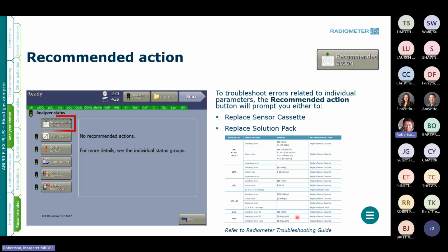So in this section, we're talking about going in, again from analyzer status, and looking at recommended actions. So if there was anything the analyzer thought it needed you to do, you can push that button. I generally say touch it at least once a day and push that button and see if there's anything in there. We'll talk a little bit about troubleshooting. Most of the time, you'll be prompted to either replace the sensor cassette or replace the solution pack. So troubleshooting on here is actually very, very easy.